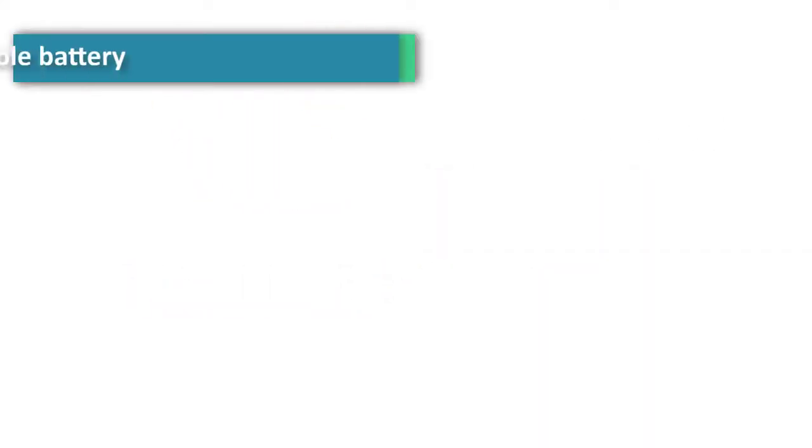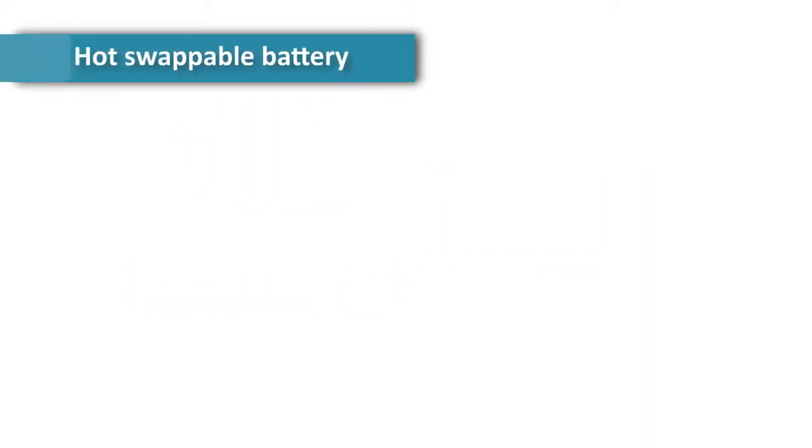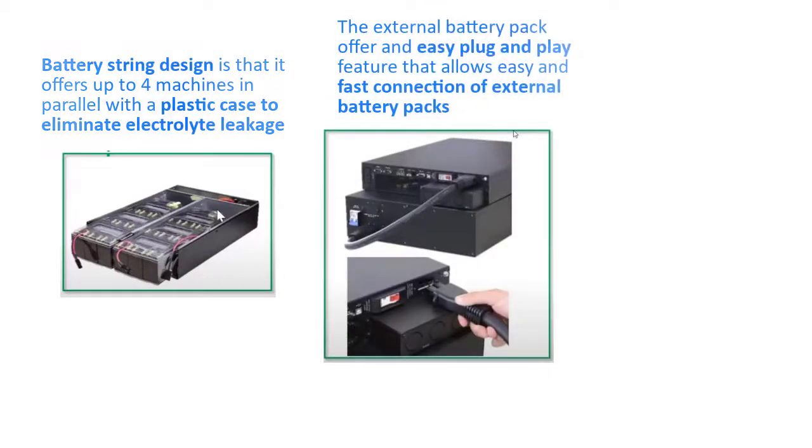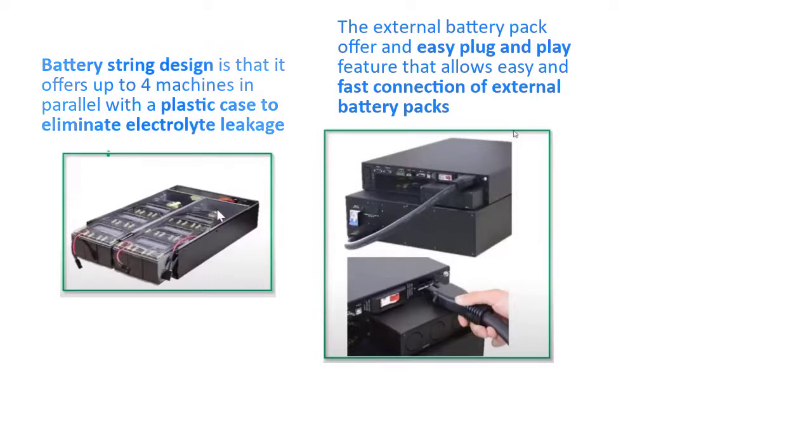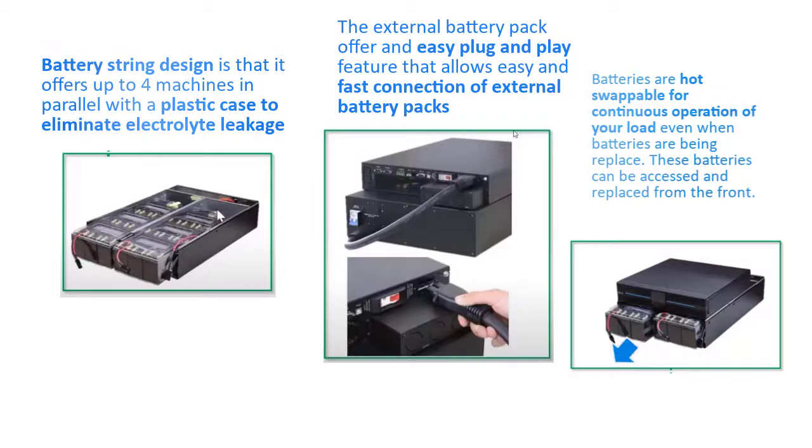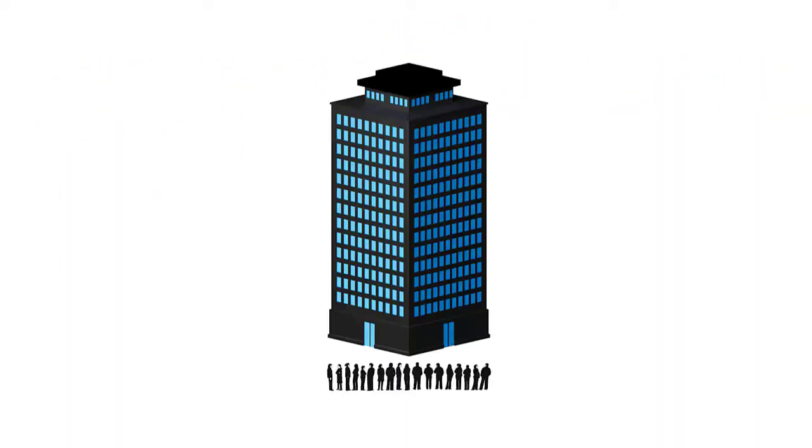We would like to show you a brief overview on the hot swappable battery and its plug and play feature. One huge benefit is that the battery string design offers up to four machines in parallel with a plastic case to eliminate electrolyte leakage. Two, the external battery pack offers an easy plug and play feature that allows easy and fast connection of external battery packs. Three, batteries are hot swappable for continuous operation of your load even when batteries are being replaced. These batteries can be accessed and replaced from the front.